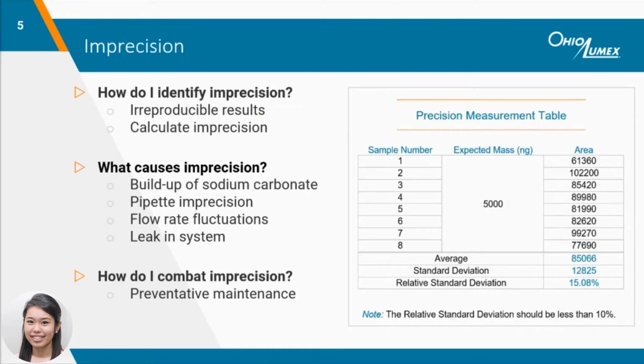Imprecision is probably one of the most common issues we see. Irreproducible results, especially when measuring continuing calibration verifications, are a telltale sign that the analyzer is imprecise. If you suspect imprecision, run 8 samples at the same level to calculate the average response, the standard deviation, and the relative standard deviation, or RSD. An RSD greater than 10% will confirm the instrument is imprecise, which is a sign to start troubleshooting. In the coming slides, we'll get into more details of each cause, as well as go over the procedures on how to improve the precision of your analyzer.